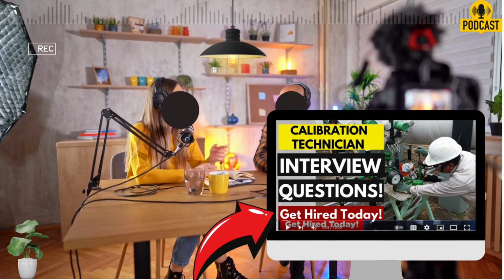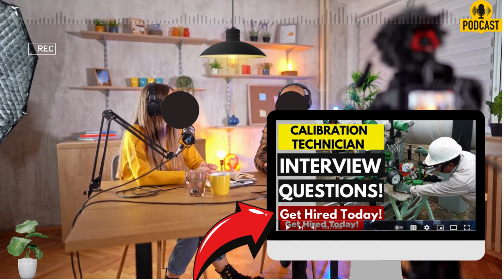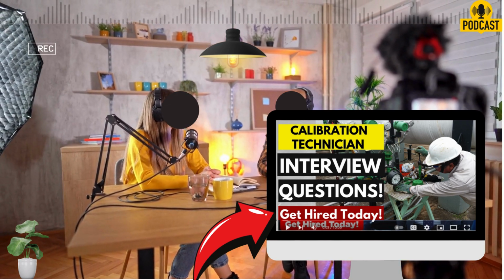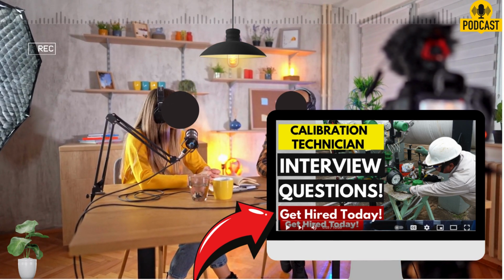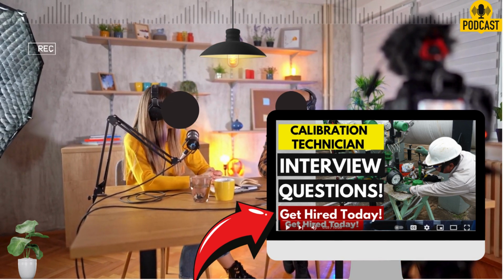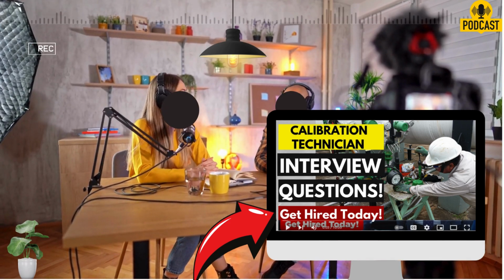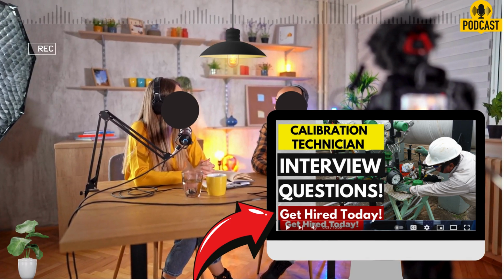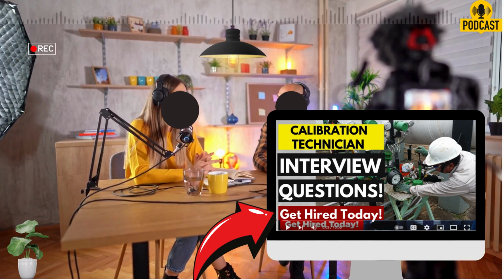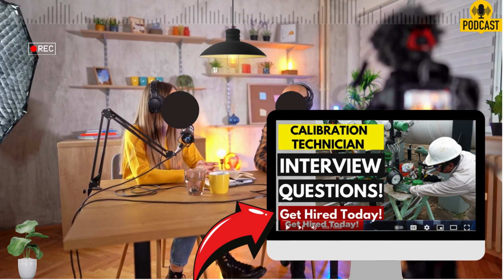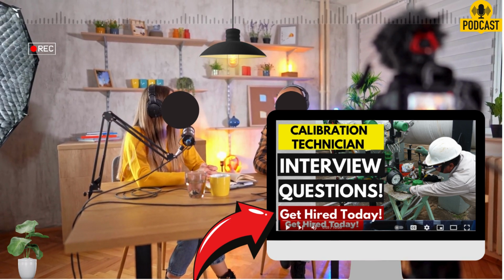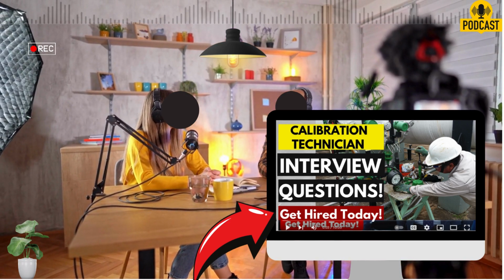That's pretty fundamental. What about the gear you use for the calibration? Does that need checking too? Oh, absolutely critical. The calibration equipment itself has to be maintained meticulously. Right, otherwise garbage in, garbage out. Precisely. If your standard isn't accurate, none of the calibrations you perform with it will be reliable. So regular checks, maintenance, and yes, even calibrating the calibration equipment itself. It's all part of the job.